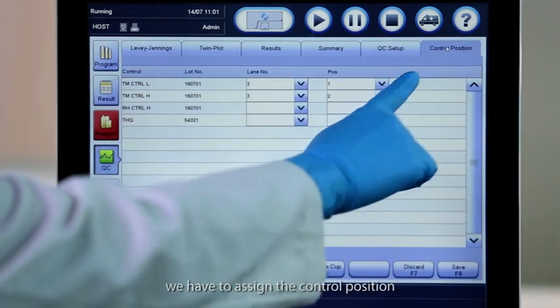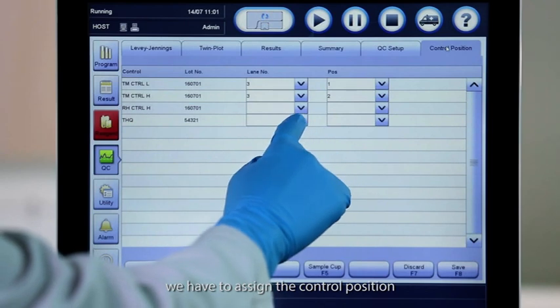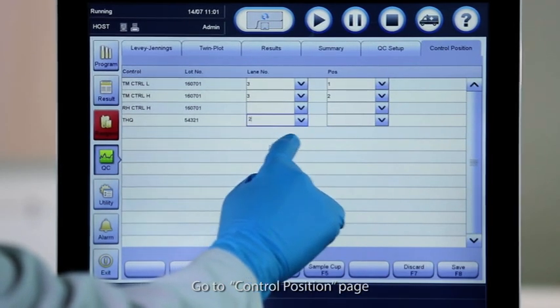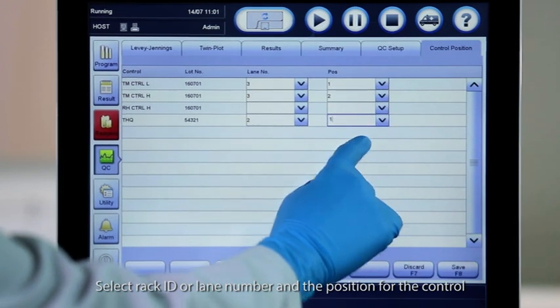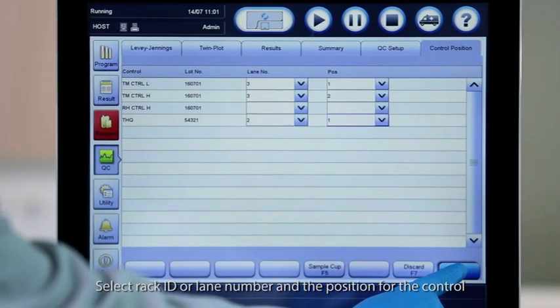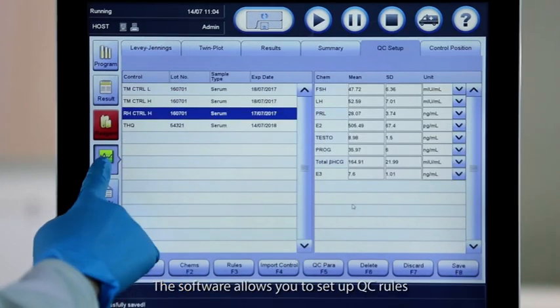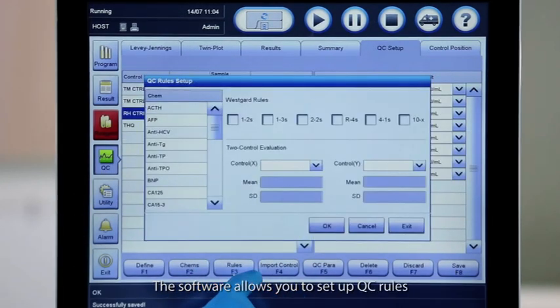Just like calibration, we have to assign the control position. Go to Control Position page. Select Rack ID or Lane Number and the position for the control.